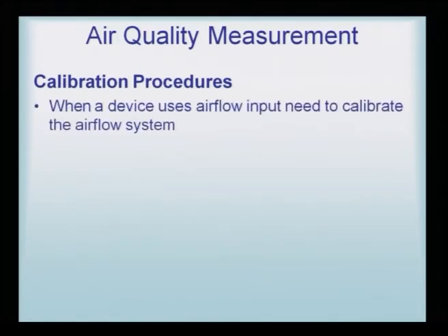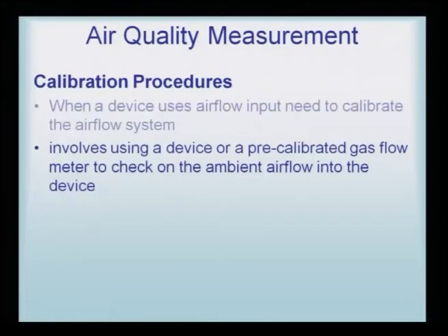Calibration procedures: any methodology which is based on comparison is actually based on calibration. When a device uses airflow input, we need to calibrate the airflow system. Obviously, if we do not have something to compare with, how would we say that the air quality is good or bad? So, for being able to discriminate the good and the bad, there has to be a comparative or calibration procedure. It involves using a device or a pre-calibrated gas flow meter to check the ambient airflow into the device. So, there is a necessity to even check whether the flow of the gas is properly coming into the collecting device, and that is done by a pre-calibrated gas flow meter connected to the collecting device.